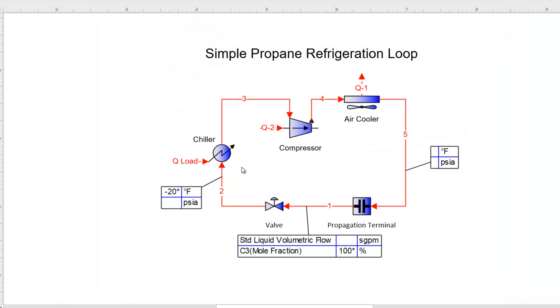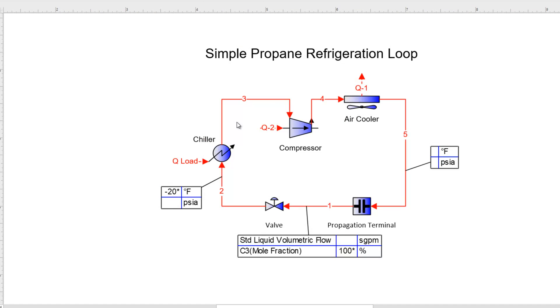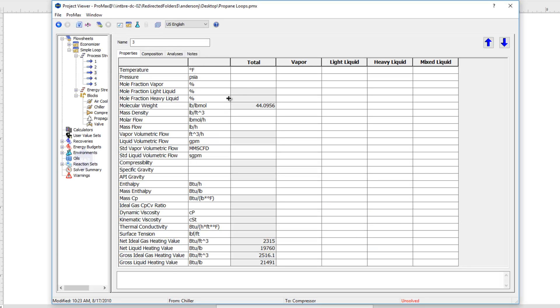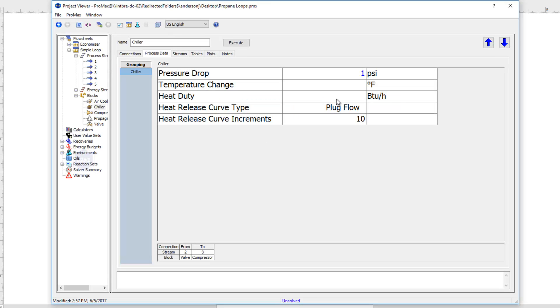That leads me to the chiller — this is the evaporator side of the chiller. Like all heat exchangers, it needs a pressure drop, so I'll put a small drop in there. We can then define what's coming out of our chiller. Since this is the evaporator side, we want our propane to be 100% vapor coming out, so I'll go into stream 3 and type 100% vapor. The last piece of information we need is how much duty the chiller needs to supply — I'm going to say 1 million BTUs per hour.